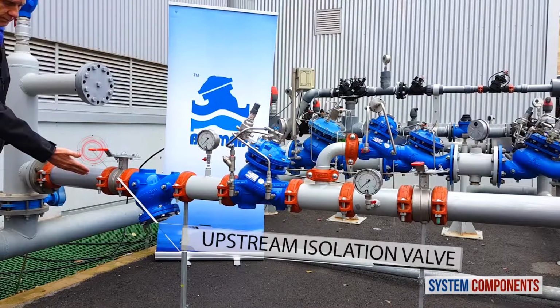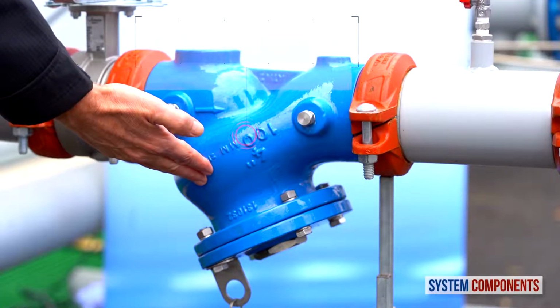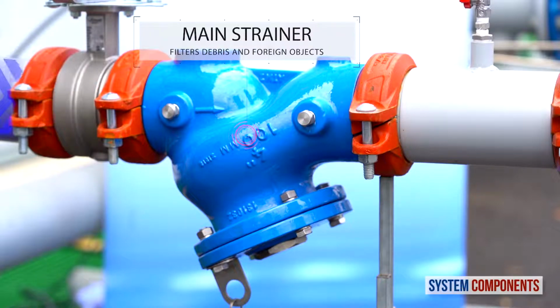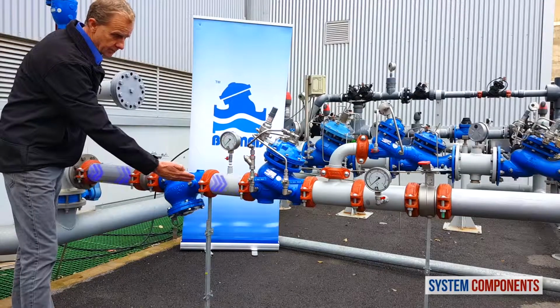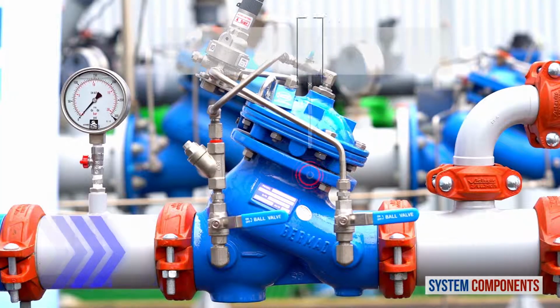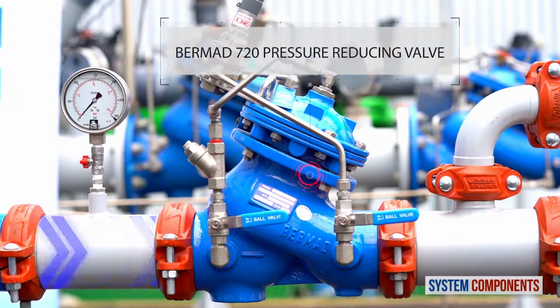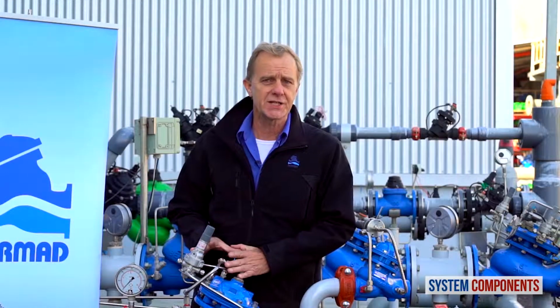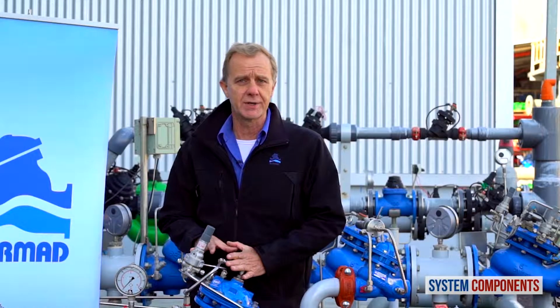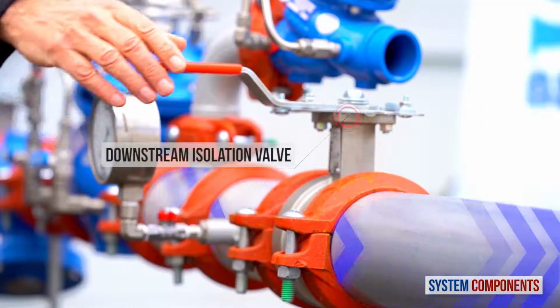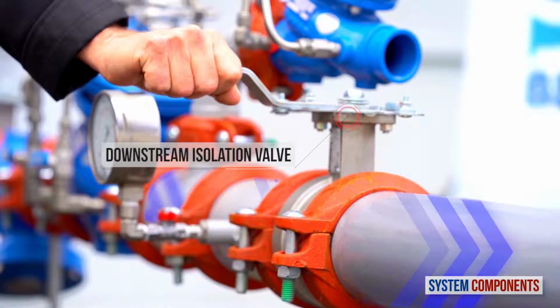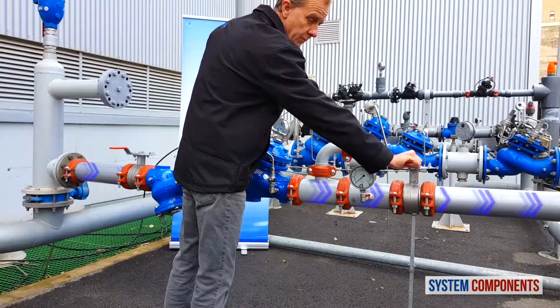When the upstream isolation valve is opened, water first encounters the main strainer, trapping any debris or foreign objects. The water then enters the BERMAD 720 pilot-operated reducing valve. It is with this valve that we can adjust the downstream pressure to the exact pressure requirement. From here, if the downstream isolation valve is opened, the water will go on to the consumer.